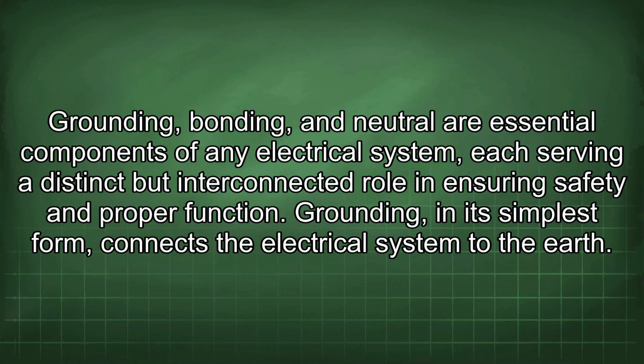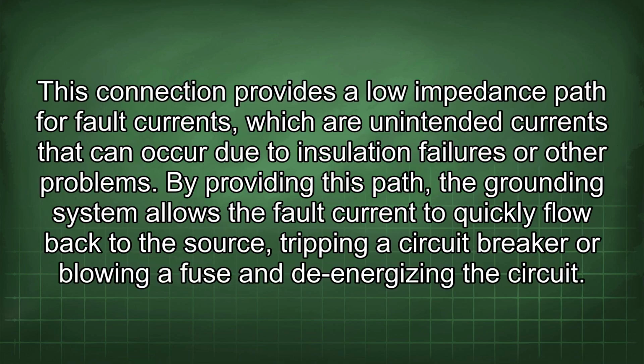Grounding, bonding, and neutral are essential components of any electrical system, each serving a distinct but interconnected role in ensuring safety and proper function. Grounding, in its simplest form, connects the electrical system to the earth. This connection provides a low-impedance path for fault currents, which are unintended currents that could occur due to insulation failures or other problems. By providing this path, the grounding system allows the fault current to quickly flow back to the source, tripping a circuit breaker or blowing a fuse and de-energizing the circuit.